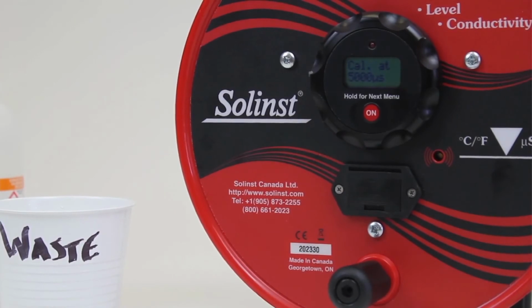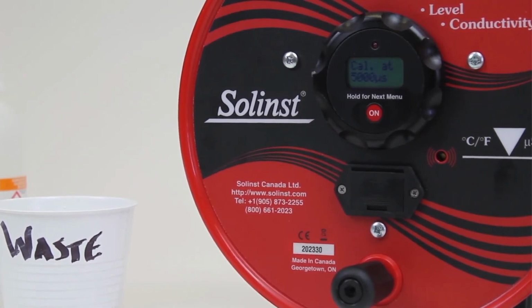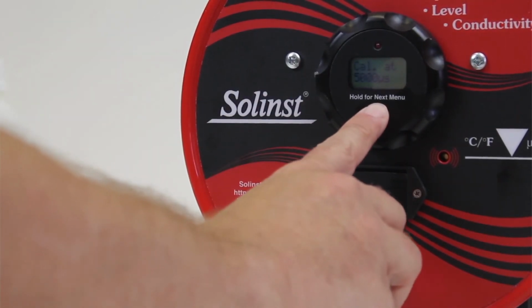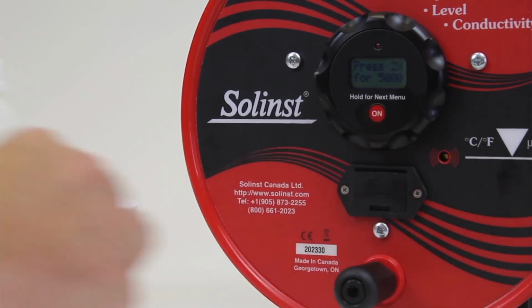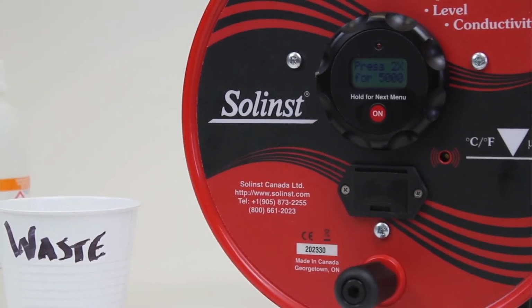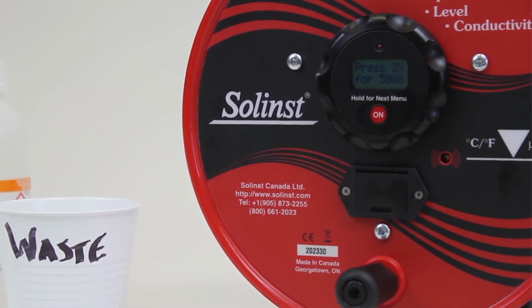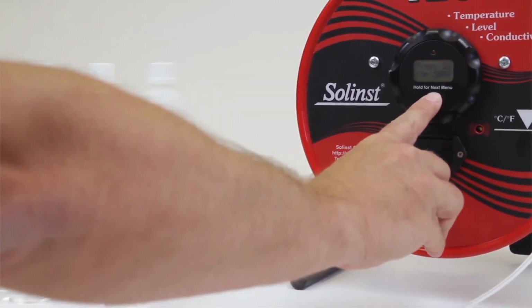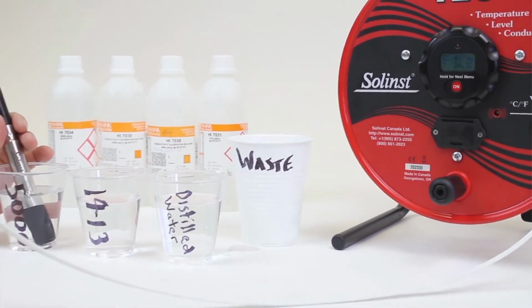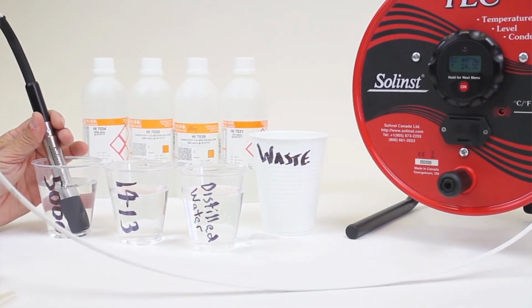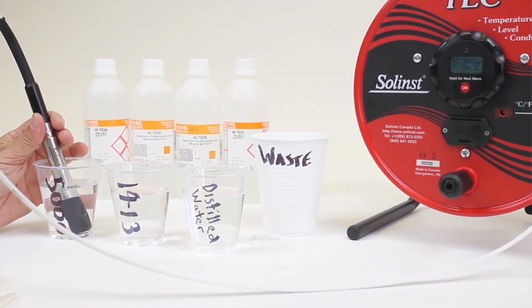Now I'm at calibrate for 5000. So to accept that, I go to the next screen, which will give me the instruction to press 2 times to lock in that calibration. So I'm going to carefully hold the probe in place and press once, twice. It's waiting while it writes that information, and now it's gone back to the main screen.